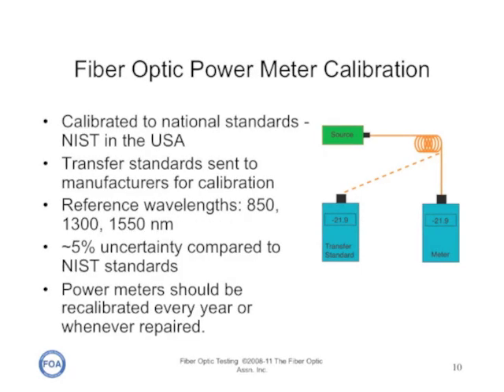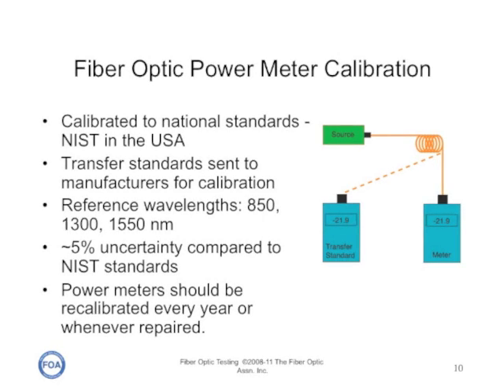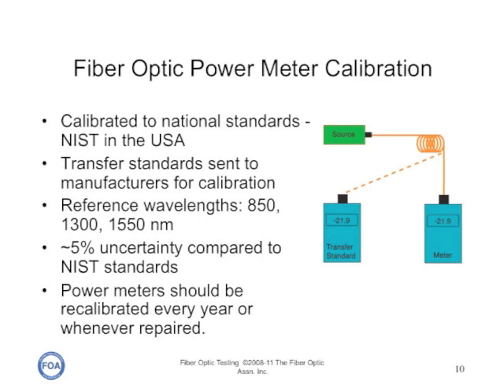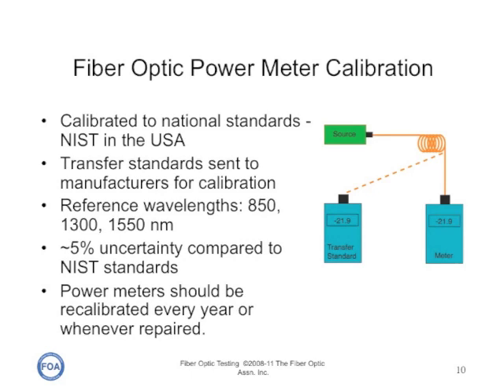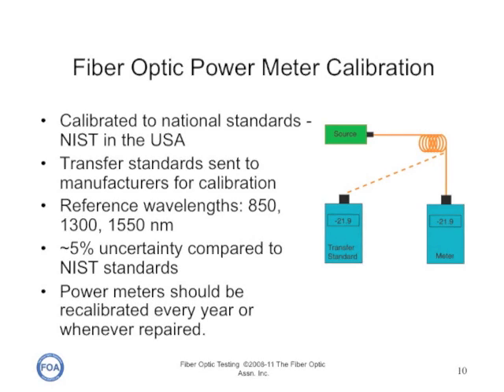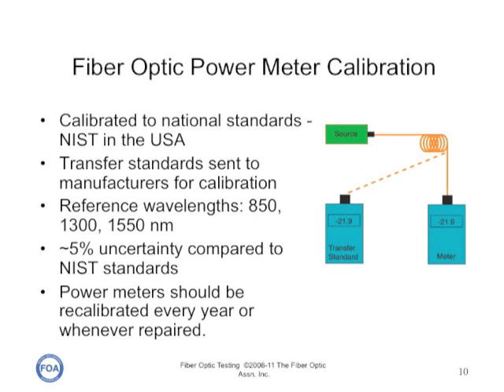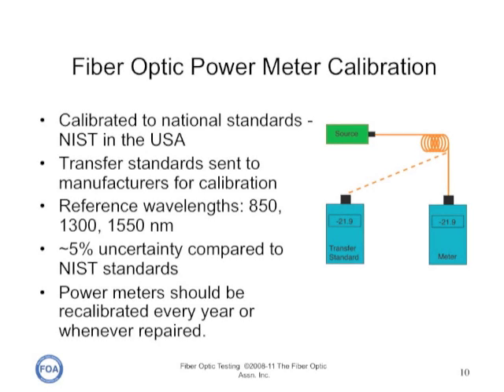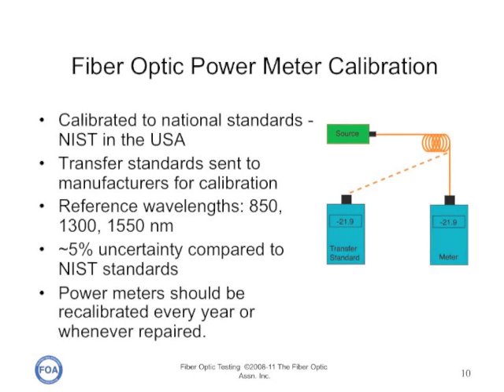Fiber optic power meters are calibrated to national standards, like NIST in the US, using transfer standards sent to manufacturers for calibration. NIST provides standards calibrated at 850, 1300, and 1550 nanometers, and manufacturers adjust their calibrations to agree with those standards. However, the process of transferring standards to manufacturers means there's typically about a five percent uncertainty compared to NIST standards. Meters should be recalibrated every year or whenever repaired.